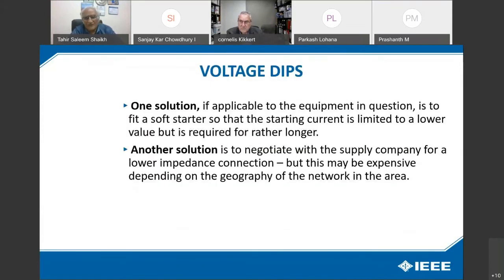One solution for this voltage dip is to have a soft starter in circuit. Your drive will run on a ramp, and there will not be much voltage dip on the system. Another solution is to negotiate with the supply company for a lower impedance connection. In our country, we don't have this concept, and no utility can give you a low impedance connection.